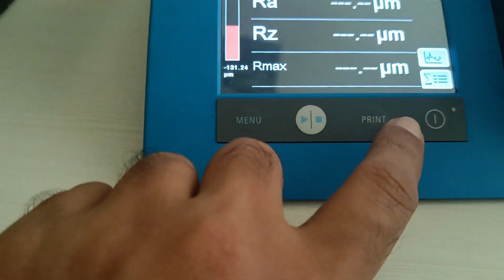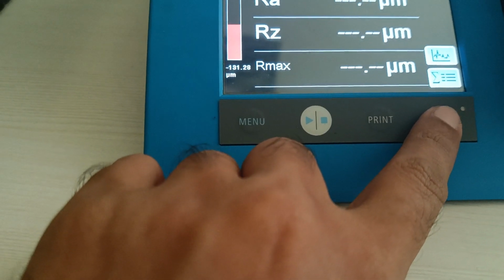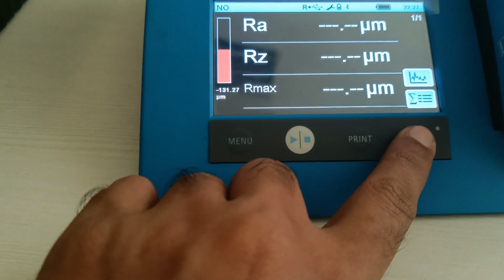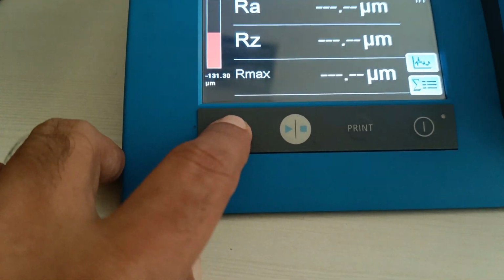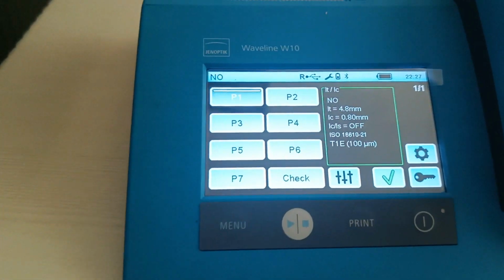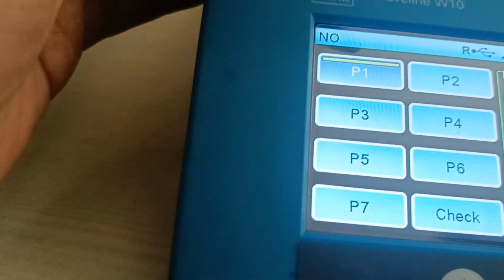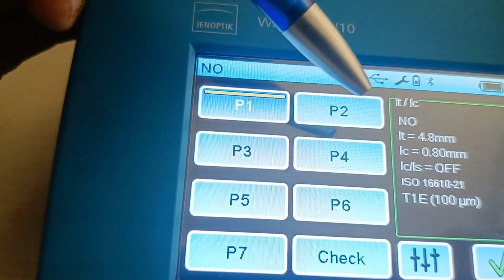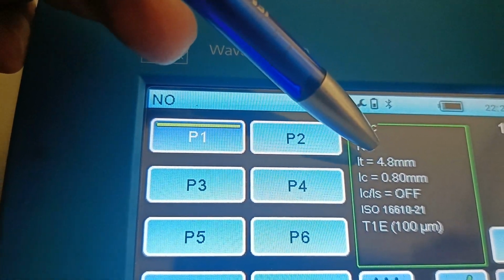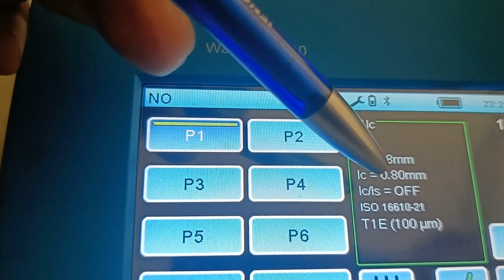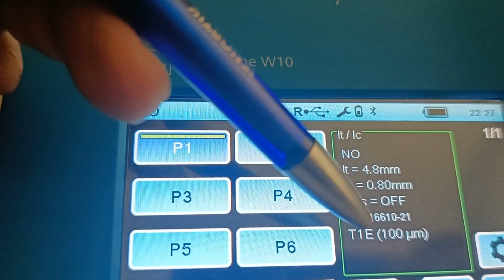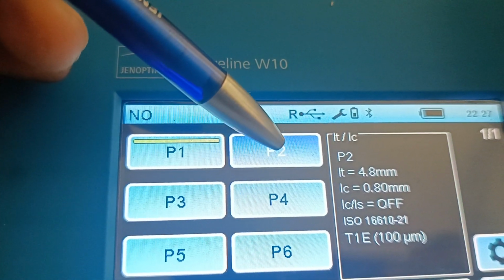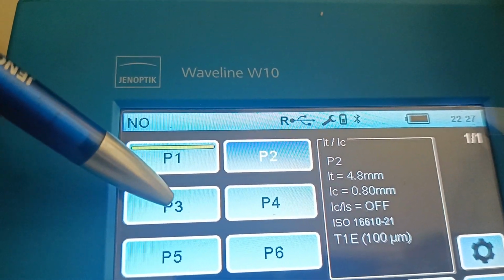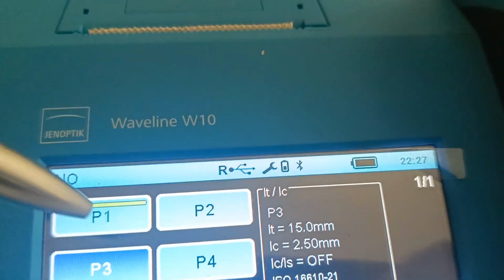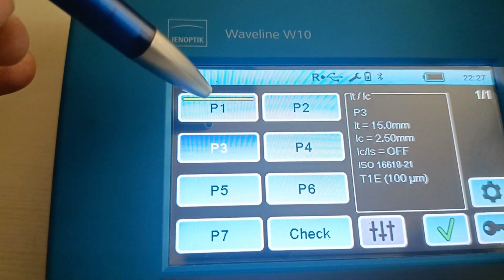So you can find the physical buttons for menu, measurement start stop, print, and power on off. If you hold the power off button again for 5 seconds, it will switch off. Now you can go to the menu. So in menu we have 8 programs. So this is program 1, and you can see the program 1's details here. The length 4.8, cutoff is 0.8, LC by LS is off, ISO, and what probe is used. So similarly, if you click P2, and P3, you can see the data changing. So whichever is in the green line, that is selected actually.